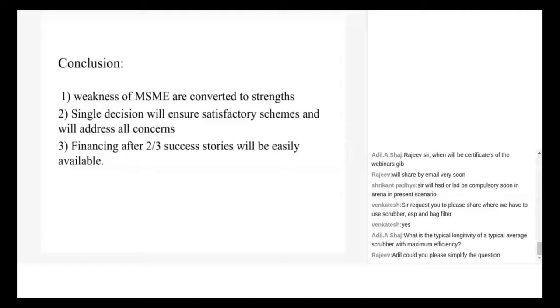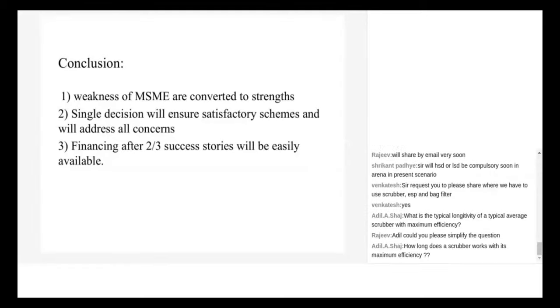Whereas with a scrubber, there are no such issues - water is there, which reduces the heat, the temperature part of it. So I would prefer you go for the scrubber, because that is the ultimate, undoubtedly the most accepted material. As I always say, if nature had given us bags, we would have been breathing through bags. Since nature gave us a wet venturi scrubber, we breathe through a venturi scrubber.